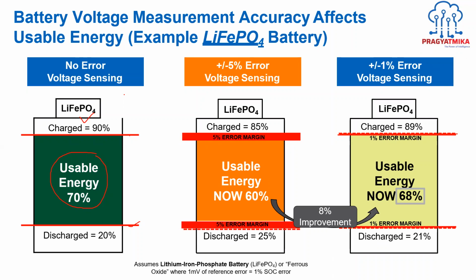This is not practically feasible. So with no error, it is 70% usable energy that you can have from your battery pack. If there is a 5% error in your voltage sensing - and BMS has to sense the voltages of your battery packs, specifically the cells - then our usable energy reduces to 60% only, because a 5% error margin can lead to the lower threshold increasing up to 25% in place of 20, and the upper threshold becoming 85 in place of 90. So our usable energy becomes 60%.